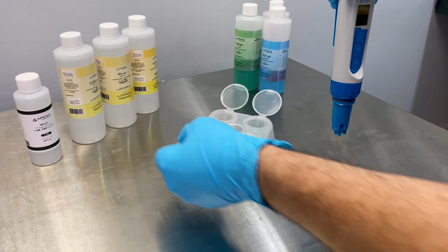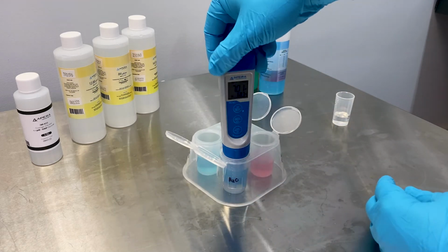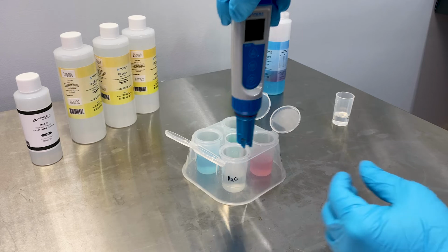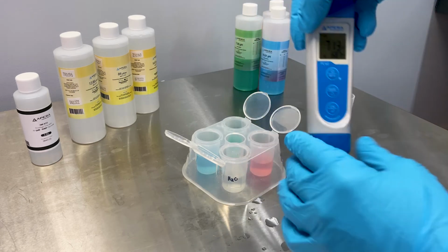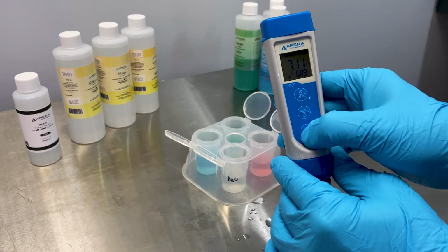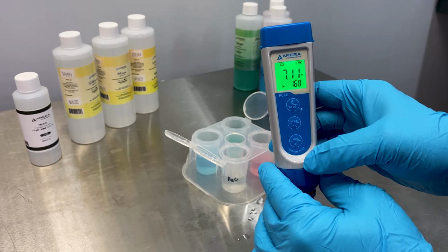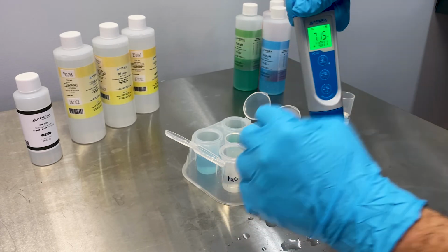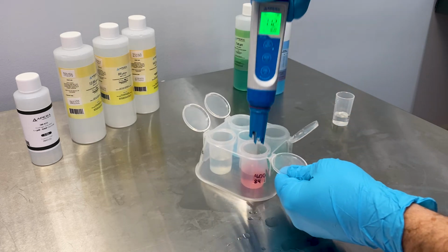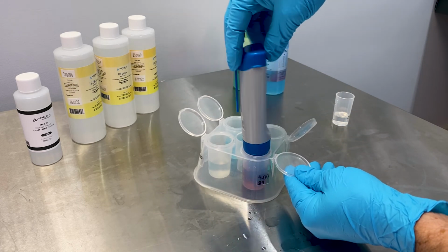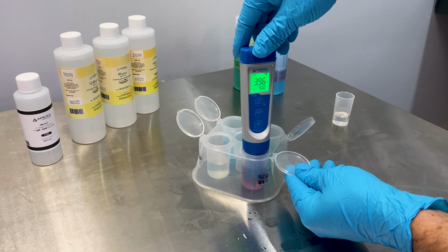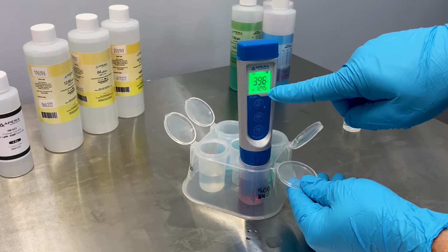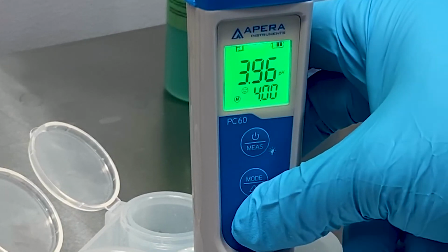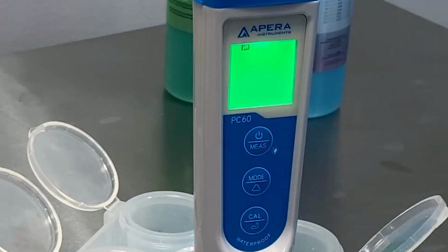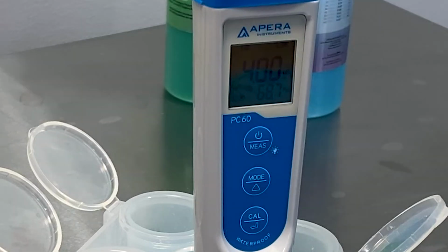Before the next calibration, I like to rinse off my meter in distilled water and gently shake it off to clean it off before it goes into the next solution. This meter requires a press of the calibration button again to put it back into calibration mode. It will flash and show what pH it's looking for next. We will go ahead and put the meter in the number 4 pH and let it start calibrating. Wait until the happy face lights up to indicate it's done, and sweet, we have one more to go. It's flashing, indicating the number 4 is done, and now I can move on to the number 10.